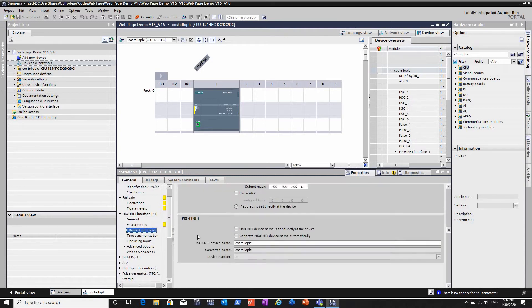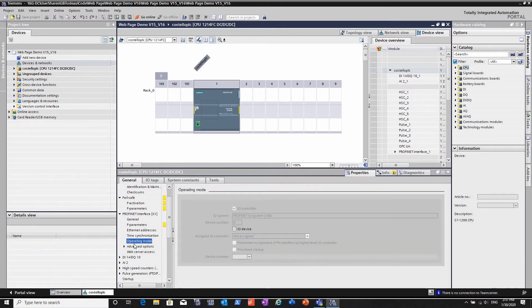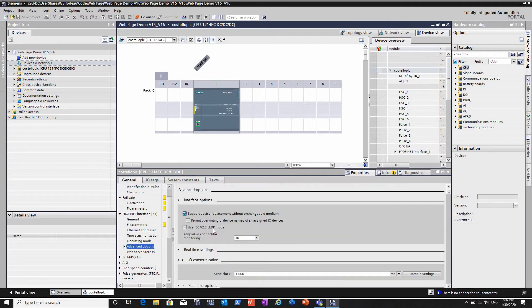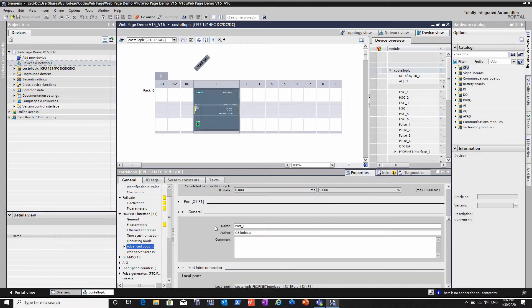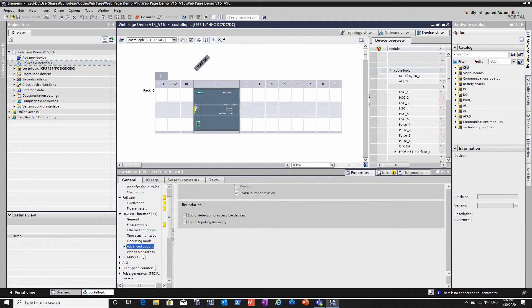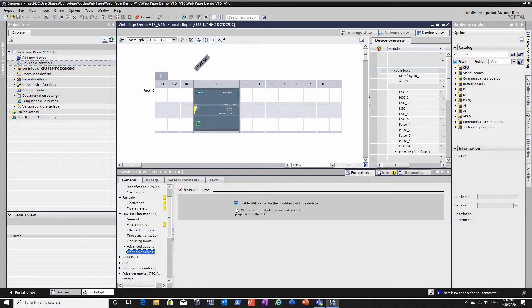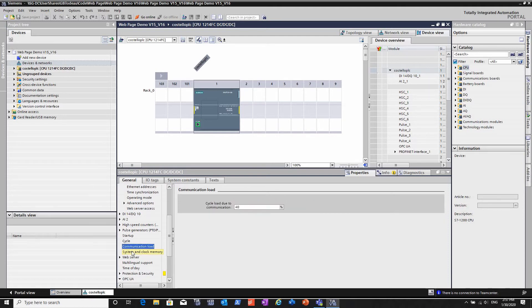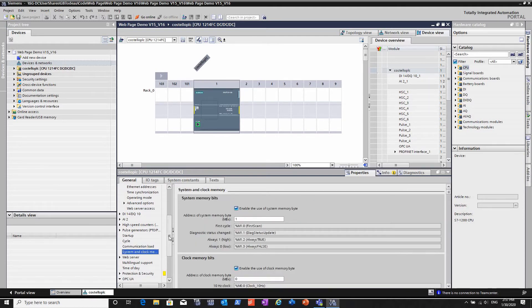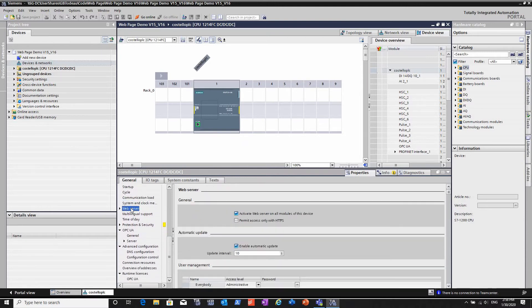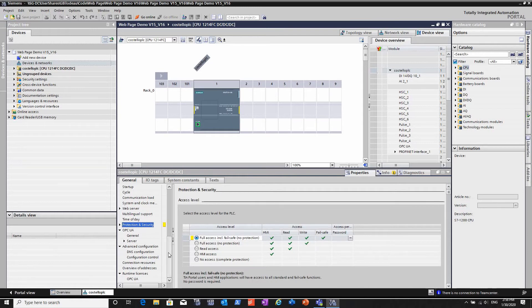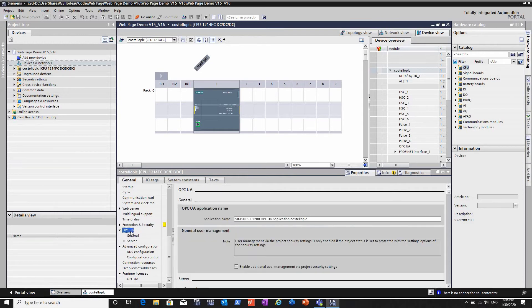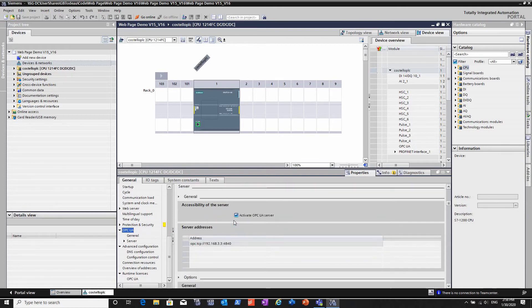I'm stepping through making sure everything was set up. Once again showing that web pages are enabled - we're running both web pages and OPC UA on the same PLC at the same time. I always check these memory bits - they come default off. Under security, when you deploy this for real you're going to want to have security on, passwords and user rights. For demo, I'm just turning on OPC UA by the checkbox.